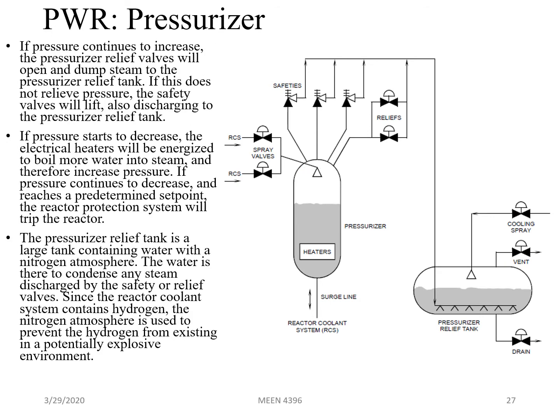Then, if the pressure continues to increase, there will be different valves on top of the pressurizer. The pressurizer relief valves will open and dump the steam to the pressurizer relief tank. Inside this relief tank, it is filled with cold water. Steam in contact with this cold water will be condensed, so that the primary loop will be discharged, and the temperature and the pressure will be maintained.